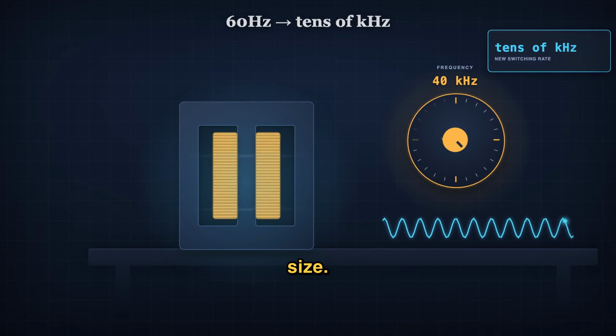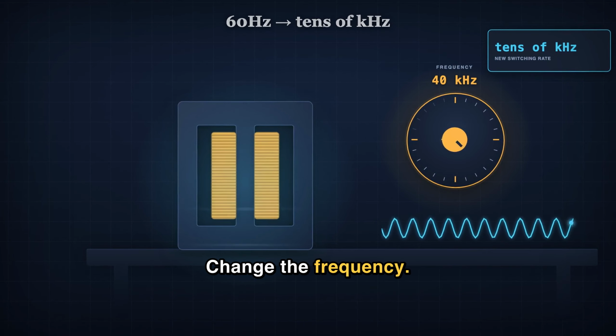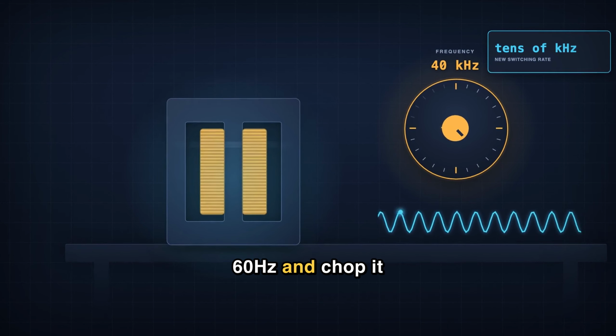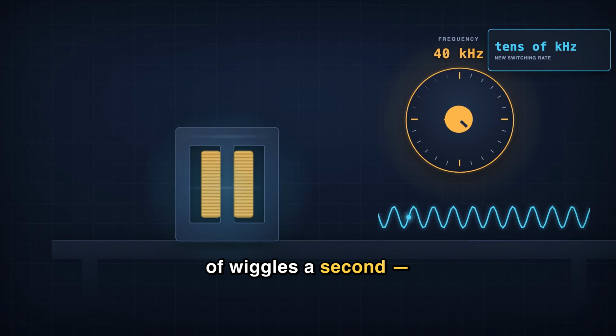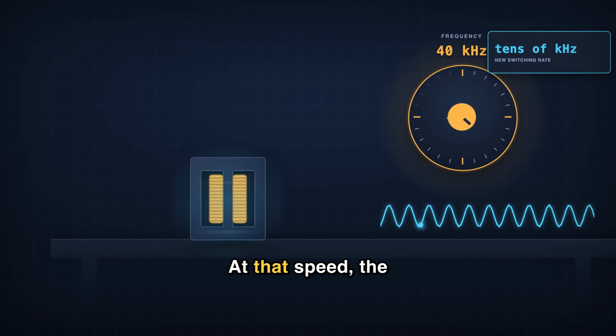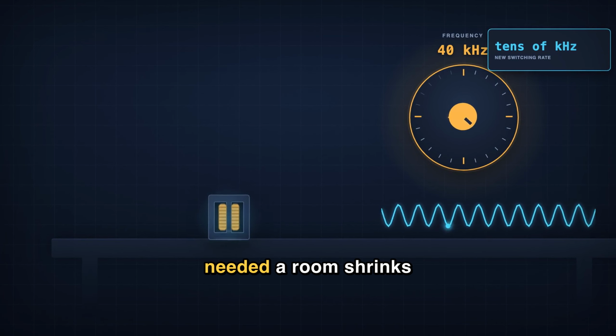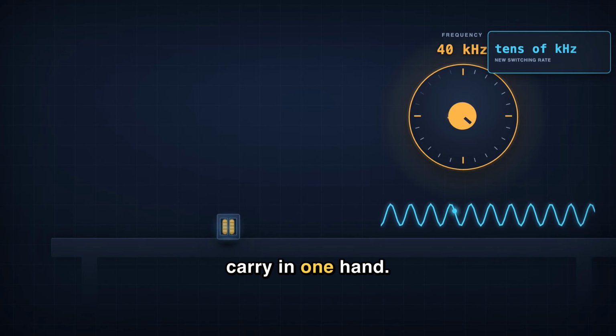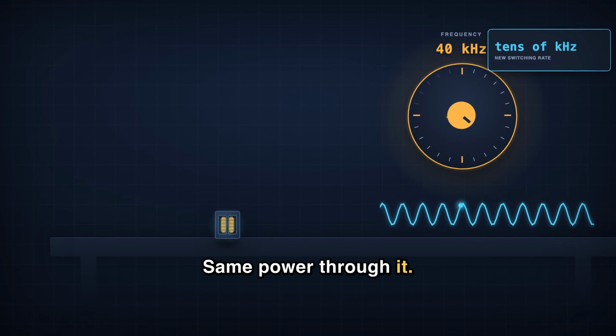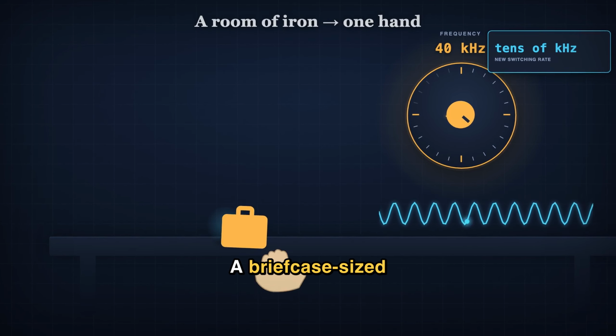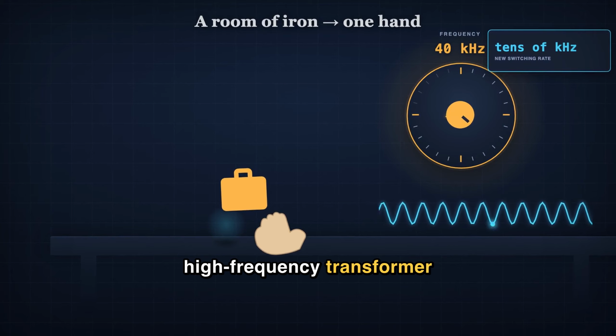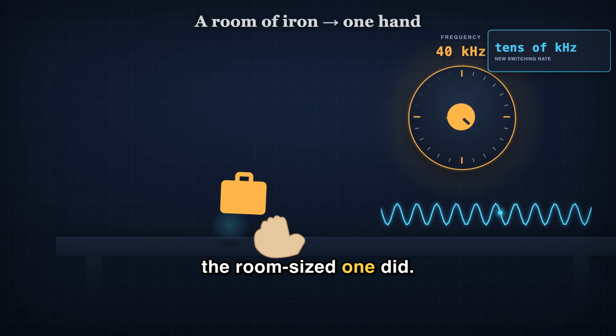So do not fight the size, change the frequency. Take the grid's lazy 60 Hz and chop it into tens of thousands of wiggles a second, tens of kilohertz. At that speed, the magnetic core that once needed a room shrinks to something you could carry in one hand. Same power through it, same job done. A briefcase-sized high-frequency transformer moves the megawatts that the room-sized one did.